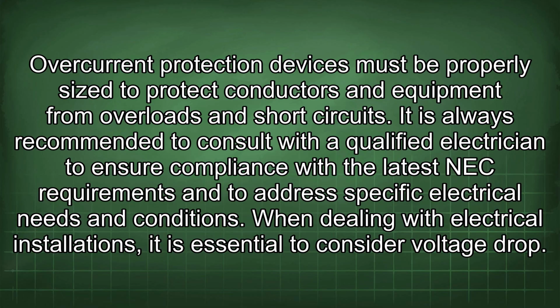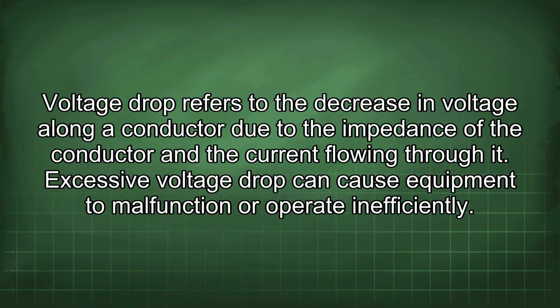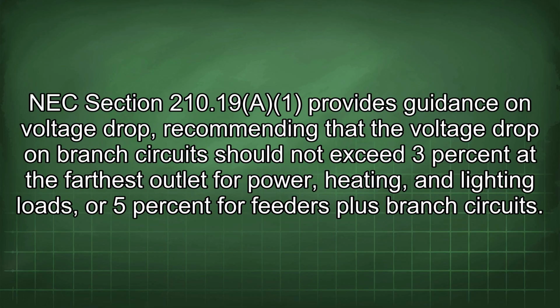When dealing with electrical installations, it is essential to consider voltage drop. Voltage drop refers to the decrease in voltage along a conductor due to the impedance of the conductor and the current flowing through it. Excessive voltage drop can cause equipment to malfunction or operate inefficiently. NEC Section 210.19(A) provides guidance on voltage drop, recommending that the voltage drop on a branch circuit should not exceed 3% at the farthest outlet for power, heating, and lighting loads, or 5% for feeders plus branch circuits.